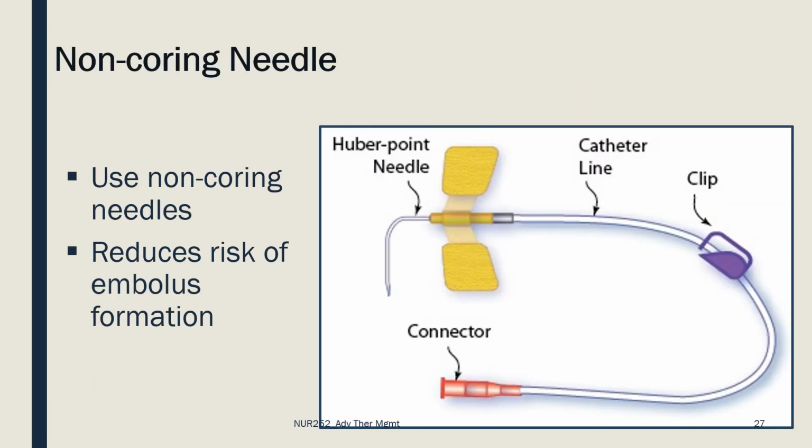Implanted ports are to be accessed by non-coring needles only. The use of standard blunt angle needles can lead to deterioration of the port, carrying with it the potential for embolization of port materials.